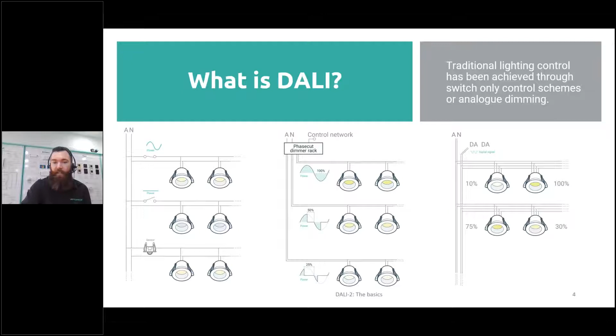So we talk about digital lighting control. What does that mean? Well, it means that the actual dimming signal isn't some sort of reference level that moves up and down. We're actually sending digital packets to each of these lights. So that means that each light will receive some sort of command, and it's going to contain an instruction. Now, the advantage of doing this over an analog system is that you don't get the noise. So even if a receiver on the other end has got quite a messy signal, so long as that signal is within the limits of what the standard sets out to actually have as a valid packet, then you are going to find it will receive it and it will execute that dim perfectly.